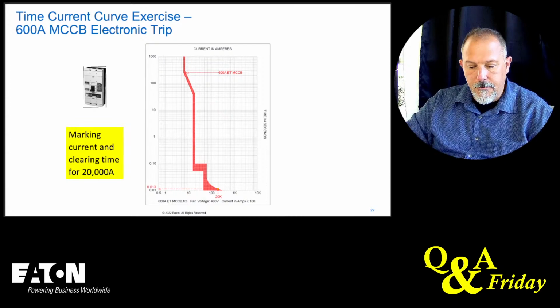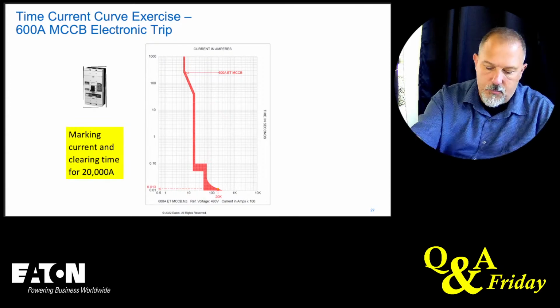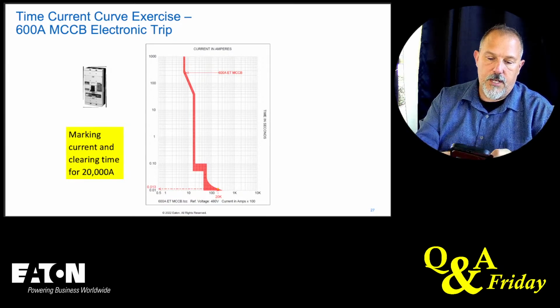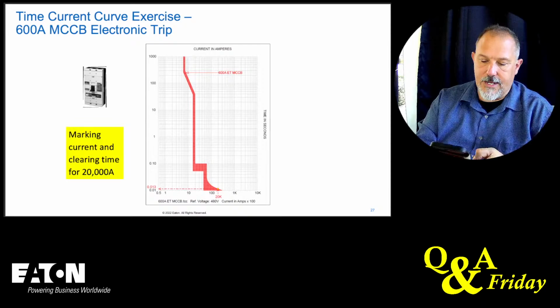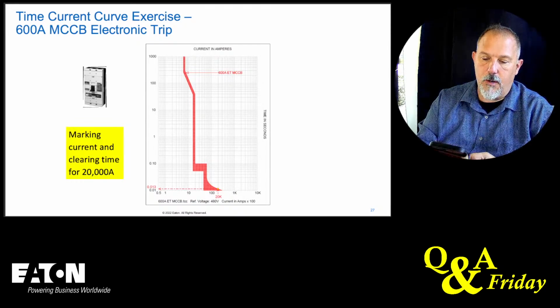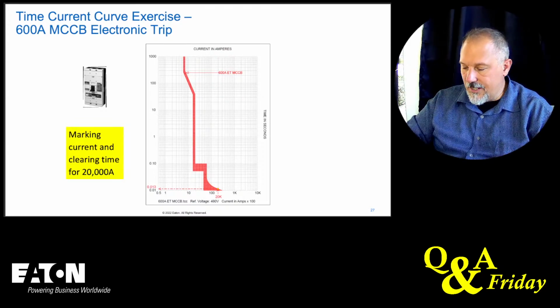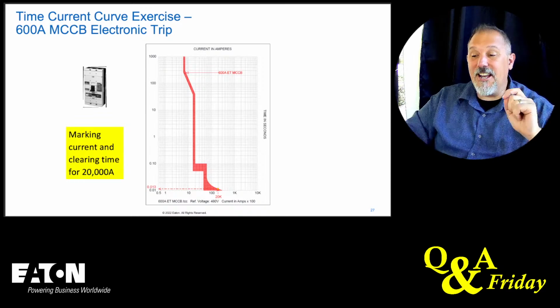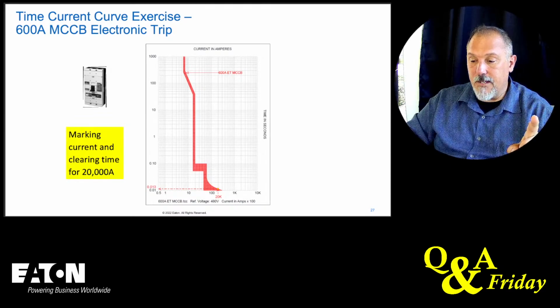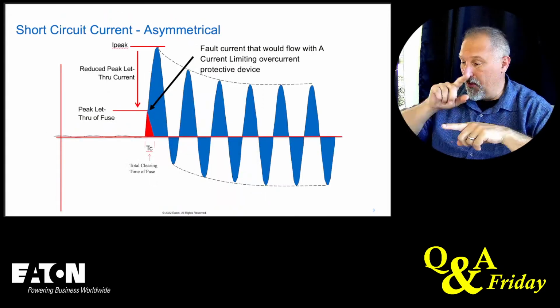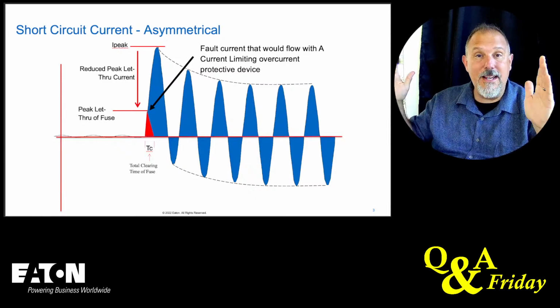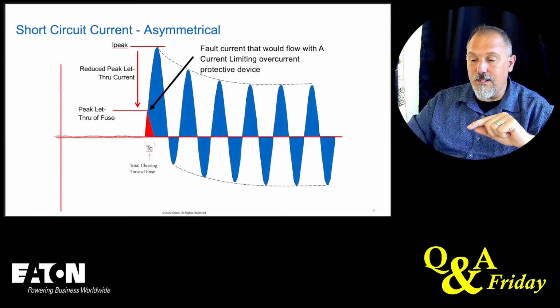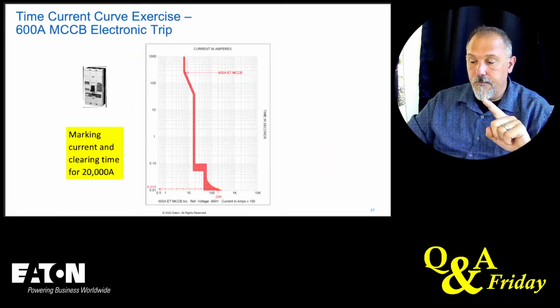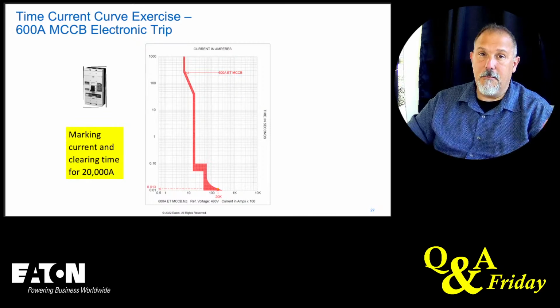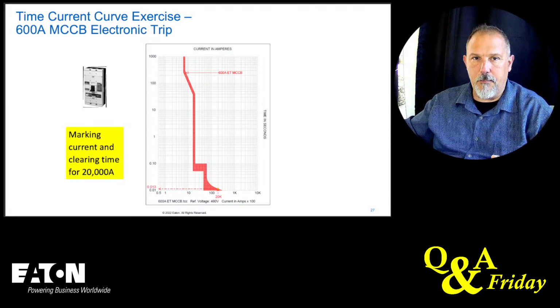Up here in the short time delay region, you're at 0.1 seconds. So how many cycles is 0.1 seconds? This is what you do. You take 1 over 60, which is 0.0167, right? And we said 0.1 seconds. So you take 1 over that and you multiply that by 0.1. That's 6 cycles. So 0.1 seconds is 6 cycles. And if you remember, 6 cycles, 0.1 seconds. Let's go back up. That's 6 cycles, all the blue. That's 6 whole cycles, 0.1 seconds. So that short time delay of 0.1 seconds for that 600 amp circuit breaker is not current limiting in that region, but it gets current limiting the higher you get the current passing through these devices.